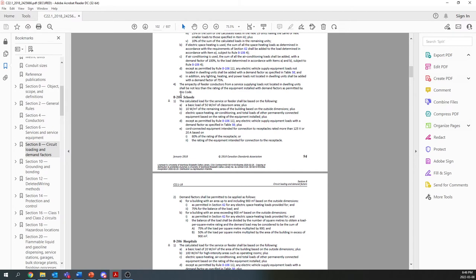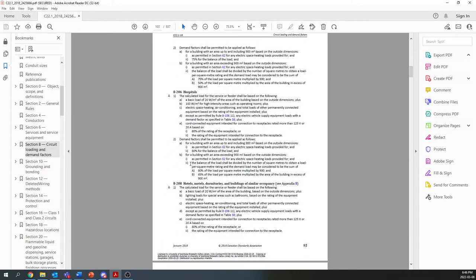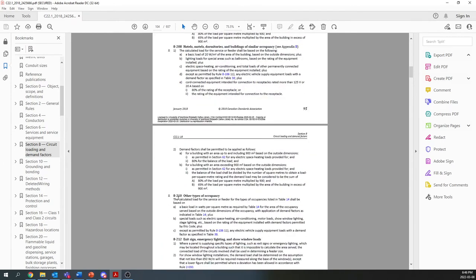Well, this allows a kind of general formula to put all those loads together that would most commonly be expected in a school, hospitals, hotels, motels, etc., and other types of occupancy. And then there's a table, table 14, that's used to generate your watts per square meter for various types of occupancies: restaurants, industrial facilities, offices, that sort of thing.